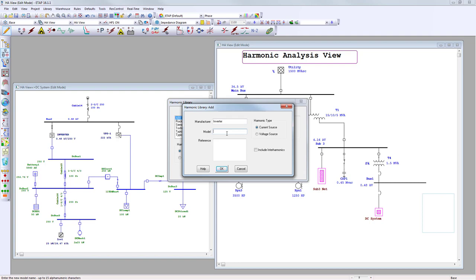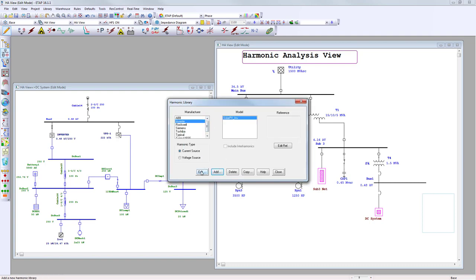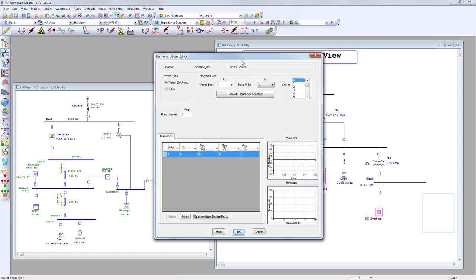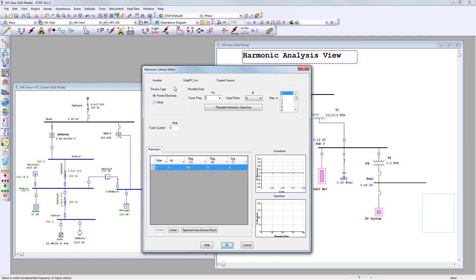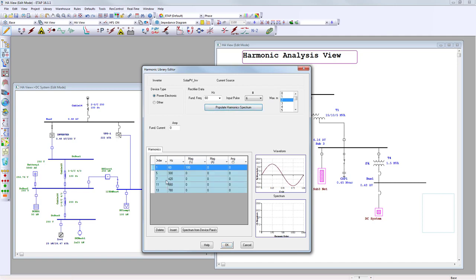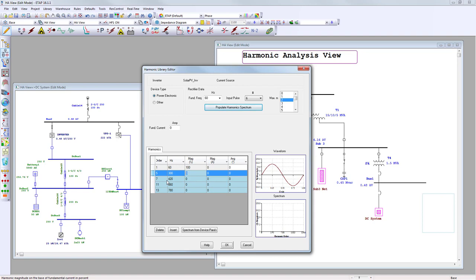The model will be 'Solar PV Inverter'. Under Reference you can put the data sheet information. This is going to be a current source. Once it's created, go to Edit. The fundamental frequency is 60 Hz, this is going to be a six-pulse configuration. Selecting 'Populate Harmonic Spectrum', we see the orders that are part of a typical six-pulse: the 5th, 7th, 11th, and 13th harmonics.